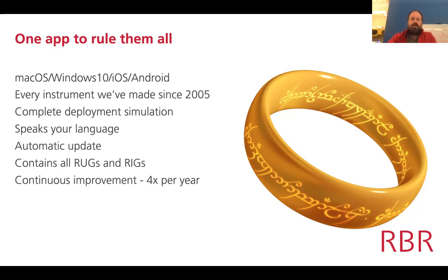One of the reasons that it is so powerful for people as users, but also before they're a user or even while the instrument is already deployed, is that we're able to simulate the deployment of any of our instruments in Ruskin without the physical instrument being around. So I'll show you a bit about that today. It's very useful for predicting the autonomy of the instrument, how long it's going to last at the sampling rates or the sensor payload that it has attached.